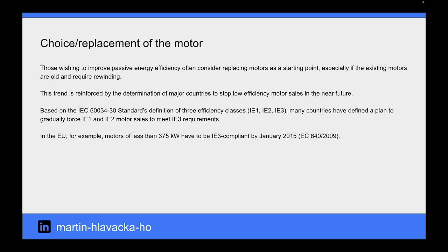60034-30 standard definition of three efficiency classes, many countries have defined a plan to gradually force IE1 and IE2 motors to meet IE3 requirements. In the EU, for example, motors of less than 375 kilowatts had to be IE3 compliant by January 2015.